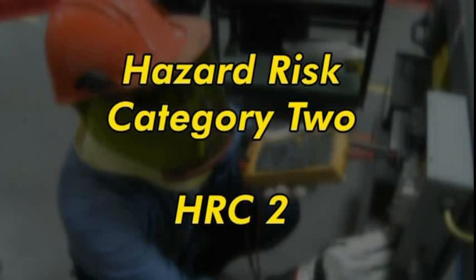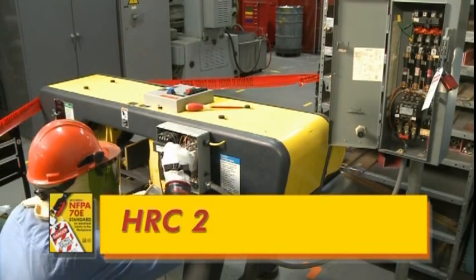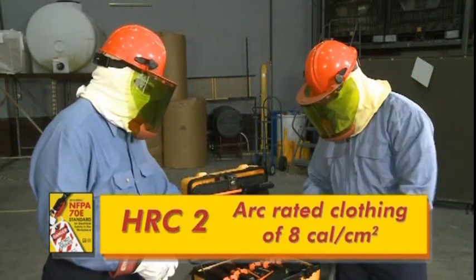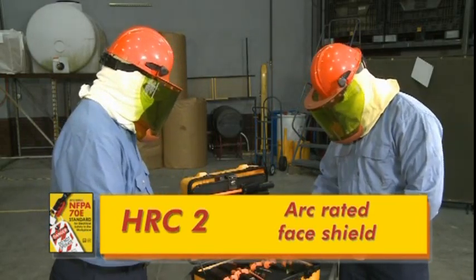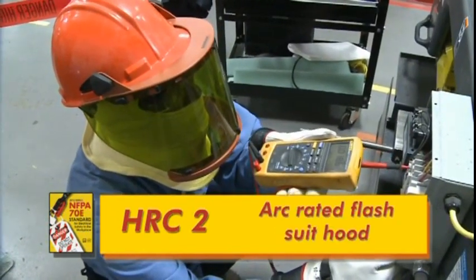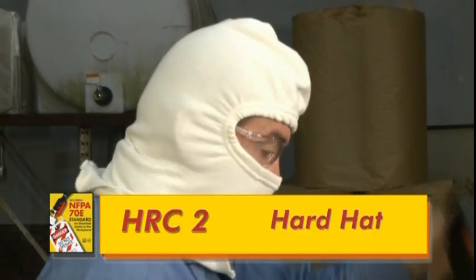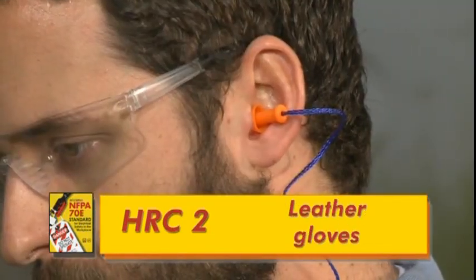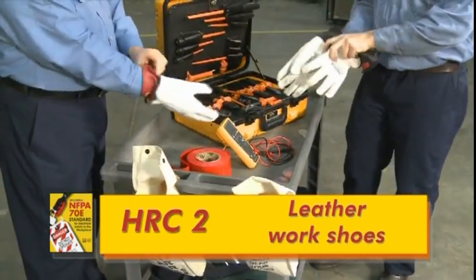Hazard risk category 2. Job tasks rated as hazard risk category 2 require 8 calories per centimeter squared of arc flash protection and an arc-rated face shield combined with an arc-rated balaclava or an arc-rated flash suit hood. Also required are a hard hat, safety glasses, hearing protection, leather gloves, and leather work shoes. It's important to note that requiring an arc-rated face shield with arc-rated balaclava or an arc-rated flash suit hood for all Category 2 tasks is a major change for the 2012 NFPA 70E. This change eliminated the hazard risk category of 2* found in the outdated 2009 regulation.